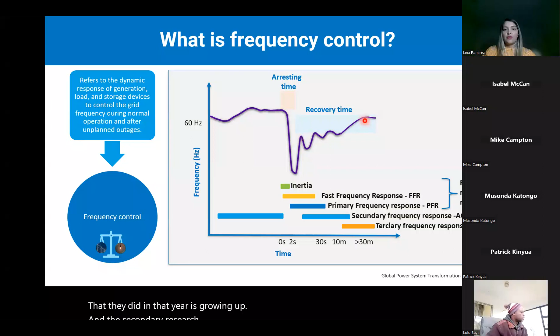So the first stage, as I mentioned, is inertia, which is provided by synchronous generation. After that, the fast frequency response, which is provided by IBR. Later, the primary frequency response, which is trying to maintain the nadir going up, and the secondary reserves, which are trying to bring the frequency back to normal values, and the tertiary reserve, which is trying to maintain the gap that we need regarding AGC.